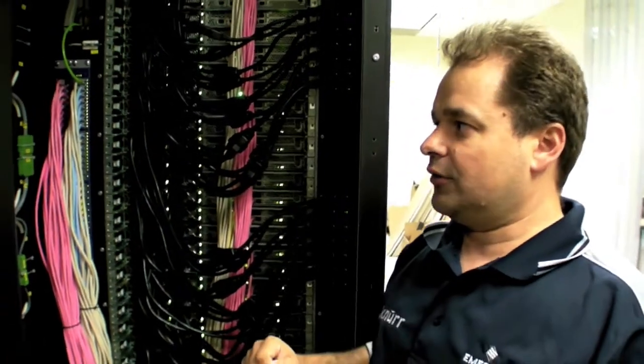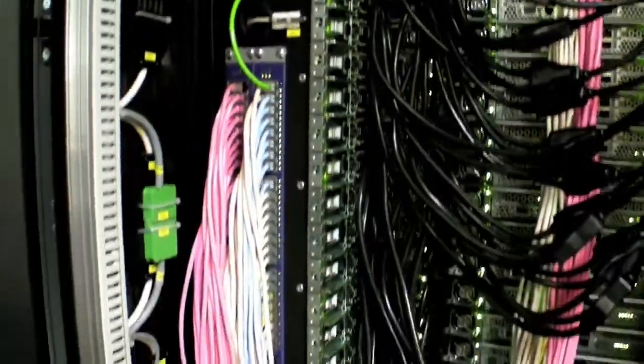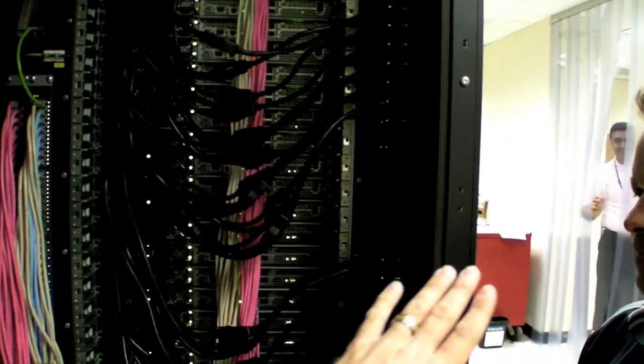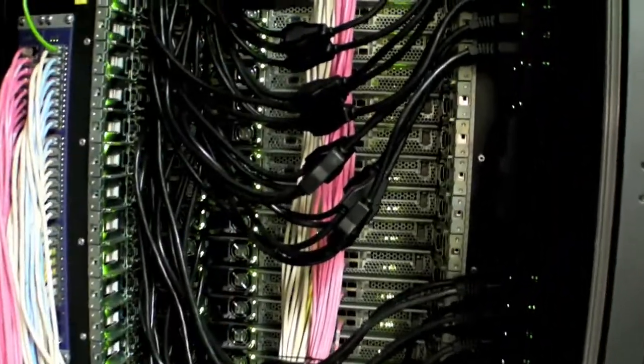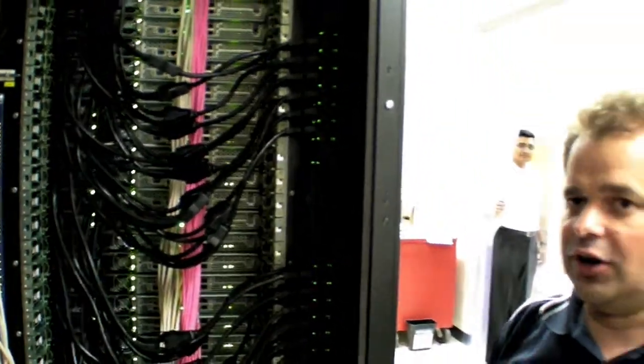This is a wider cabinet with cutouts for devices, including switch infrastructure and PDUs — currently ServerTech PDUs are installed. This creates a clear airflow path for cooling. The main challenge is cables potentially blocking airflow, though the fans are strong enough to handle it. Proper cable management is important to keep the air path clean into the fans.